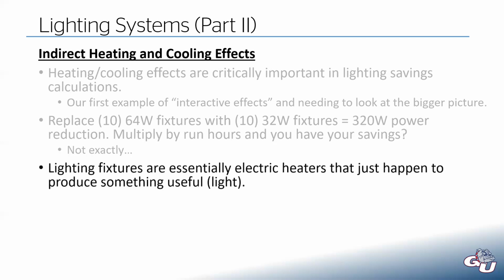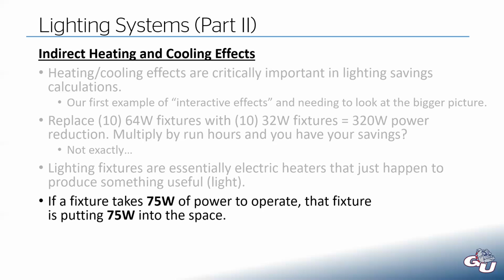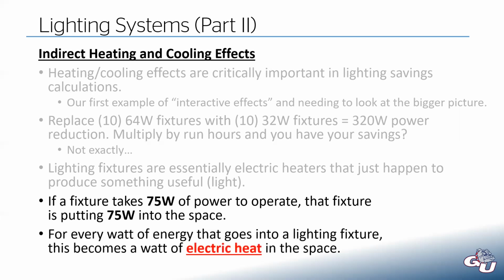As a reminder, light fixtures — if you look around your room right now at the lamp on your desk or the light above your head — that is essentially an electric heater that happens to put out light. The purpose is to put out light, but fundamentally it's also putting out heat. If you're feeding that fixture 75 watts of power, you're putting 75 watts into the space. Some of that power directly turns into heat and some into light, but as the light hits all the objects in the room, it eventually turns into heat too. So for every watt that goes into the lighting fixture, that becomes a watt of electric heat in the space.